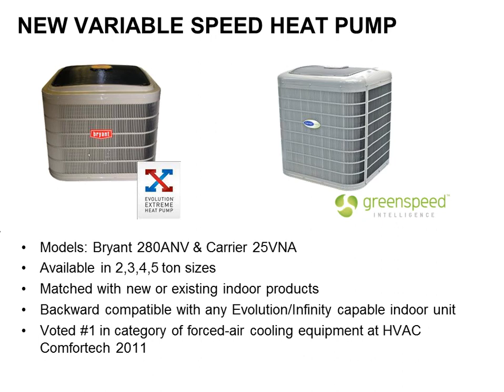These heat pumps do need to be paired up with an Evolution or Infinity communicating indoor unit. So that could be a fan coil or it could be a furnace, but it has to be a unit that has that type of controls in it because we're going to be coordinating a lot of variable speed things at one time here to kind of make it all work. There's going to be variable speed compressors, variable speed condenser fans, electronic expansion valves, indoor blowers, and all those things have to be coordinated together to make sure we're getting this thing to operate correctly at the right airflow speeds and so forth. So you do have to have an Infinity or Evolution furnace or fan coil, and you have to have an Infinity or Evolution controller on the wall in lieu of a standard thermostat.